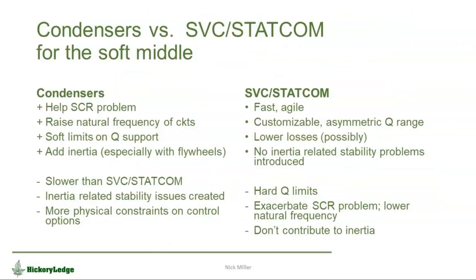Okay, so let's get to a summation here of what we might be trading off in the condenser and the SVC world. On the left side is plus and minus with the condenser. So the condensers help the short circuit problem. They actually raise the natural frequency, which is better for the control of the inverters. They don't have hard limits and they add inertia, which could be a good thing. On the other hand, they're slower, they have more physical time constants to deal with, and they have inertia. So depending on the problem you're dealing with, the inertia can be good or bad, and you have more constraints on the knob. Whereas the SVCs on the other side and STATCOMs are very agile and very fast, but they don't contribute to any short circuit.